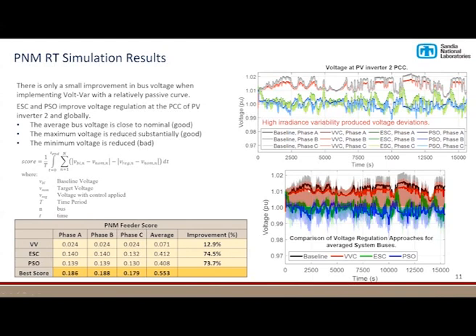When you add volt-var curve, which wasn't a very aggressive curve, you improve that a little bit. However, if you use the extremum seeking control, you can see the probing signal's impact on the average bus voltage here. But it tends to get very close to nominal voltage at 1 PU. And then particle swarm optimization is the blue line here. It also does a reasonable job of pulling the voltages close to that nominal value.